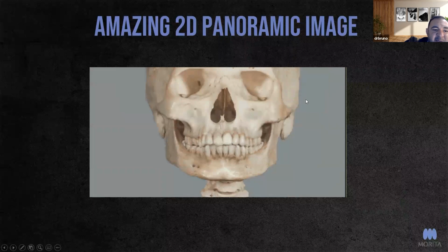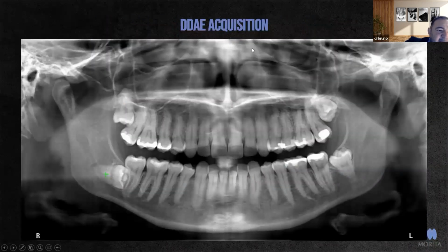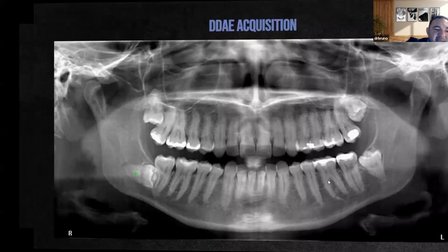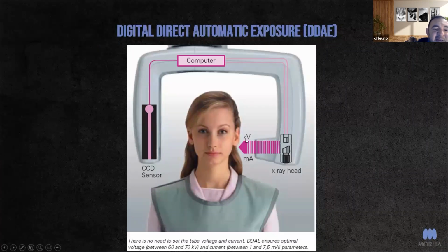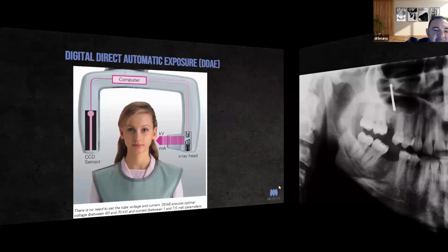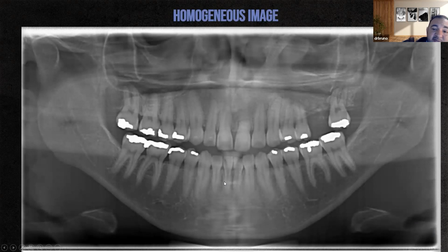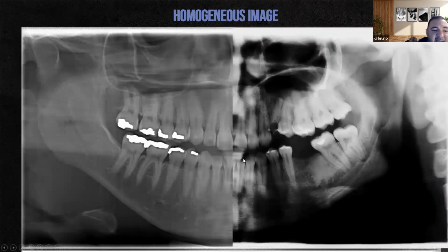Another thing that's important about panoramic imaging from Morita is the fact that it has this direct acquisition module. The direct acquisition module has to do with the fact that the KV and MA is being corrected in real time when you take a panoramic image with Morita, and therefore you have a very homogeneous density on your panos. So you don't have burnout areas with your panoramic image. The idea is, as the machine rotates around the patient's head, KV and MA is being corrected real time. So it's not uncommon to see this type of problem on competitor systems where there is a lot of burnout, or sometimes the image gets overexposed. Where on Morita, if you've done the panoramic correctly, everything gets homogeneous from a density perspective. So therefore, when you are taking a scan and you actually compare side by side, this is preferable.